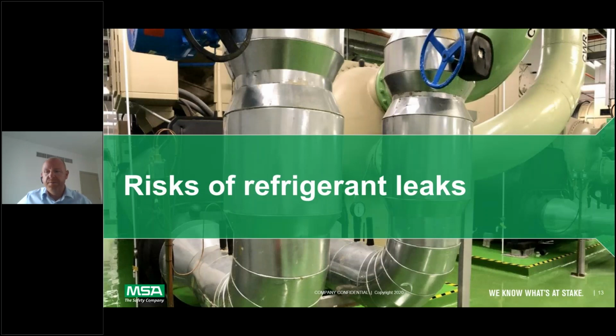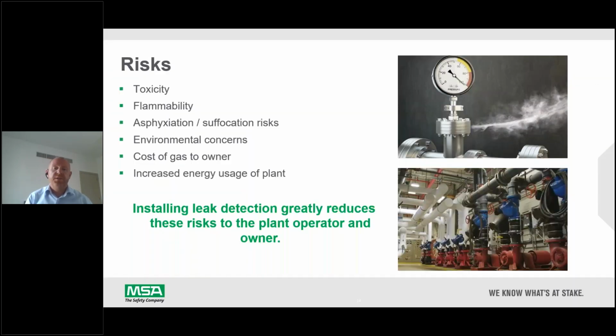So the risks of refrigerant leaks. The risks of a refrigerating system leaking in your machine room or in your plant are the toxicity of ammonia mostly, or R123. You have a flammability risk of some of the newer refrigerants. With all refrigerants, you have an asphyxiation or suffocation risk. And then there are now environmental concerns due to the high GWP of some of the gases, the cost of gas to the owner, and the increased energy usage of the plants. So installing some kind of system which detects the refrigerants at low levels greatly reduces all these risks to the plant operator and the owner.